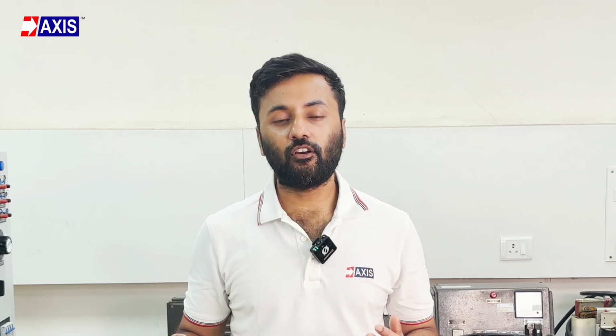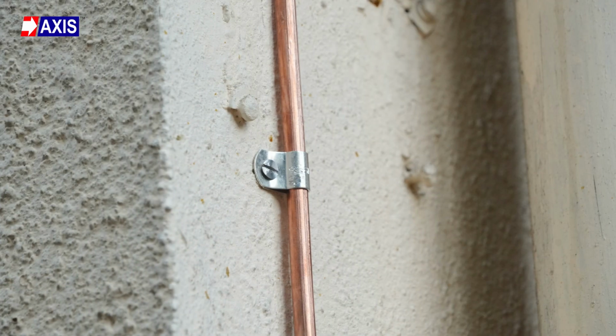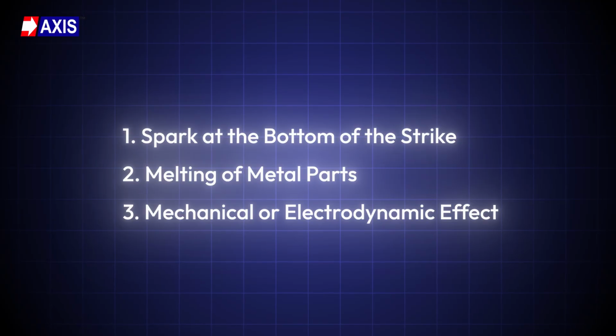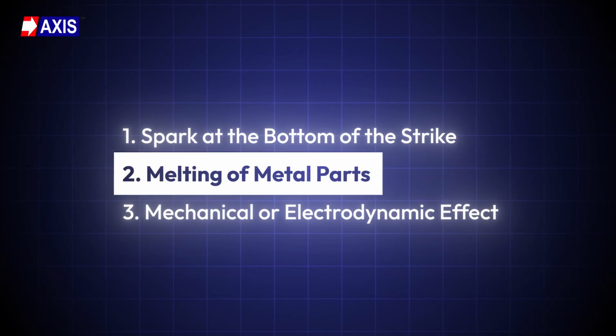When lightning hits metal, the current jumps through the air and creates a spark. That spark burns the surface. And if you see this, expect damage along the path of that current. The down conductor, surge protection devices, and nearby electronics may also be affected. Number 2. Melting of metal parts.